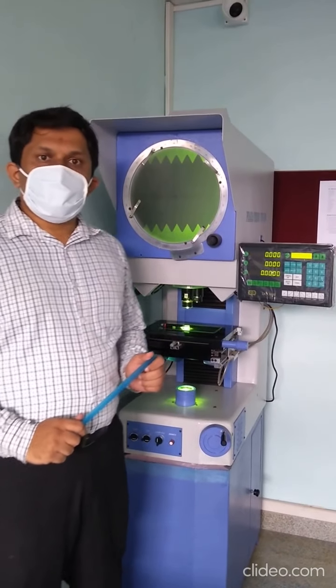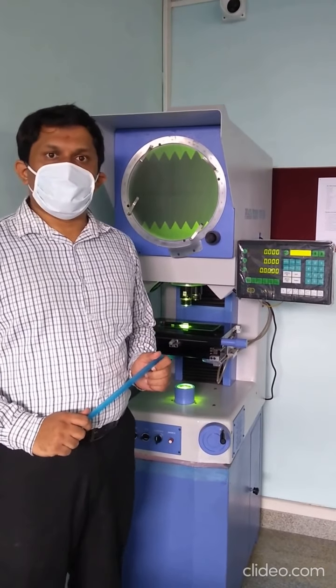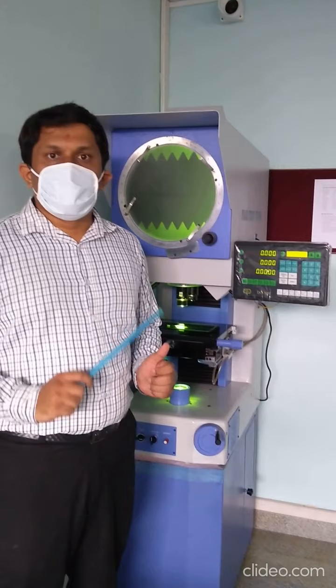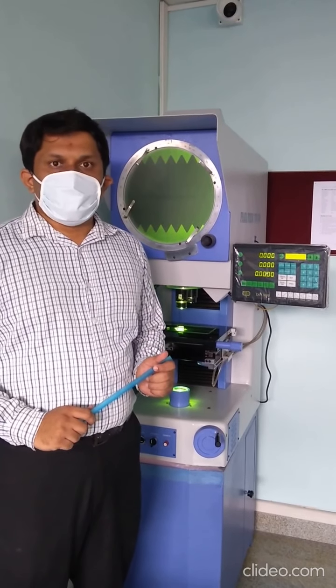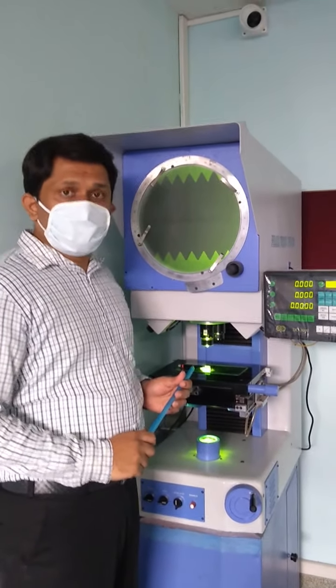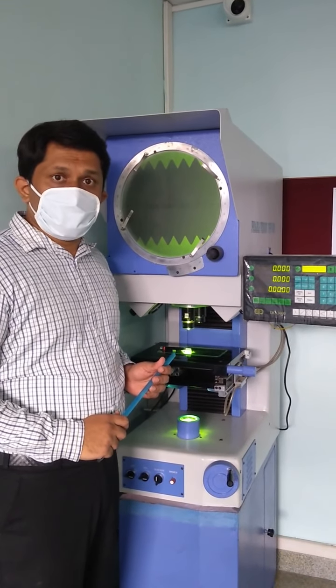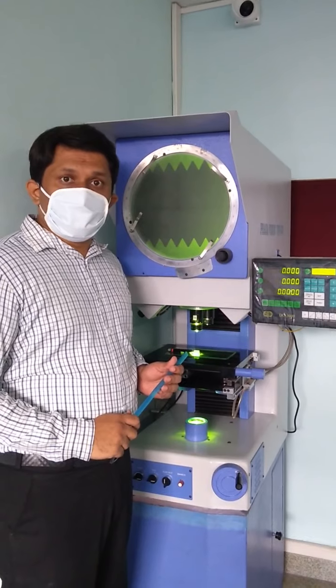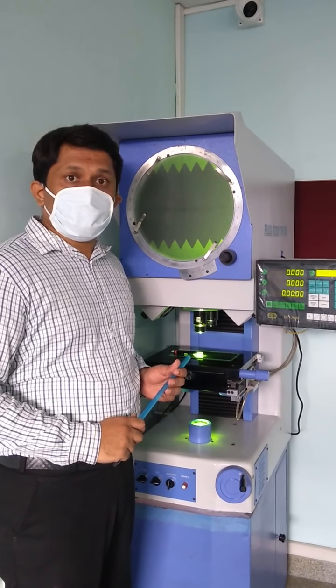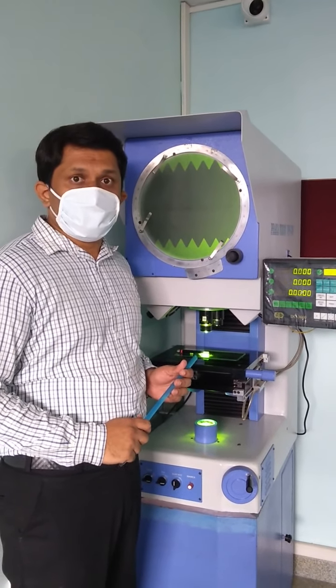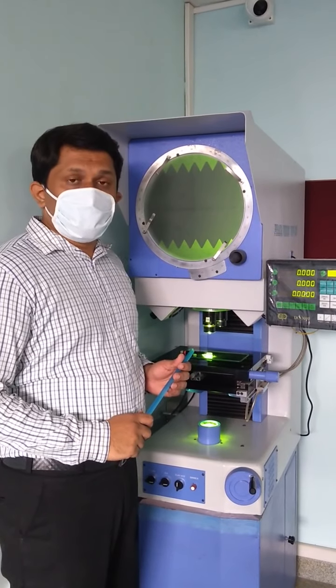Profile Projector is an optical comparator that uses the principle of optics to inspect the manufactured part. In this optical comparator, the magnified silhouette of the part is projected upon the screen and the details like geometry and dimensions are compared with the prescribed limits. So silhouette refers to the outline of the part.